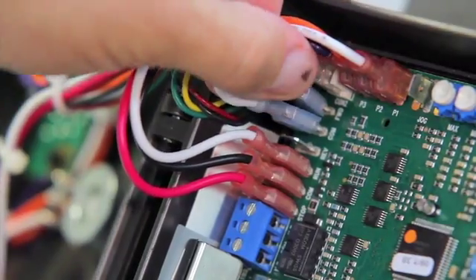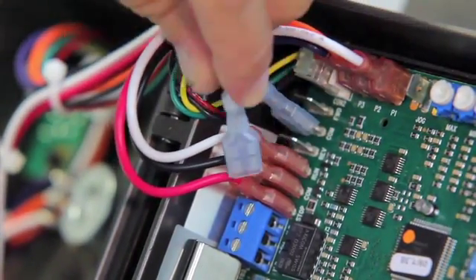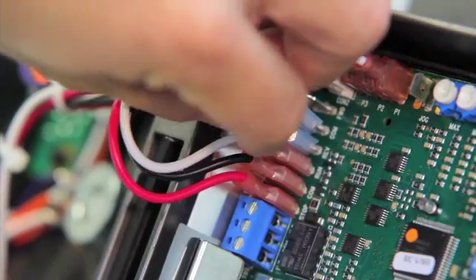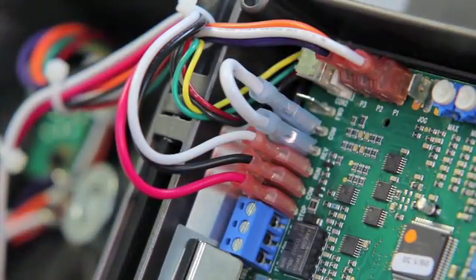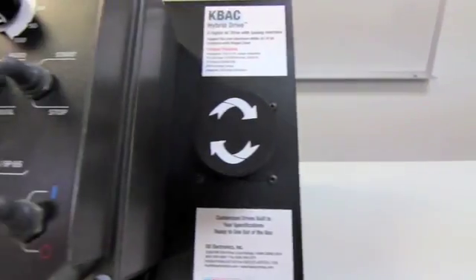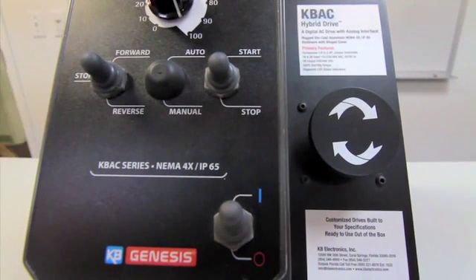You can also change the rotational direction by moving the jumper from the forward and COM position to the reverse and COM position. This feature is also available on drives that have the optional forward stop reverse switch installed. Just reverse the forward and reverse leads.